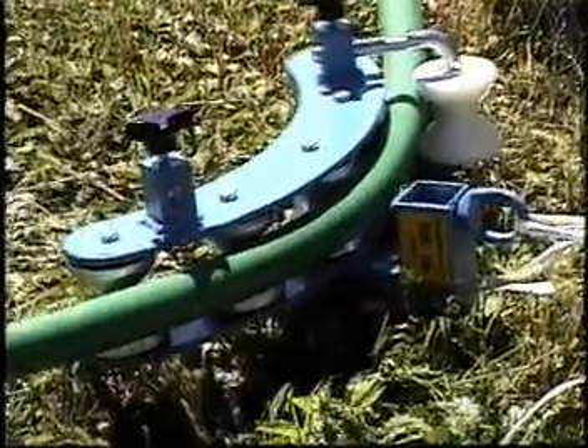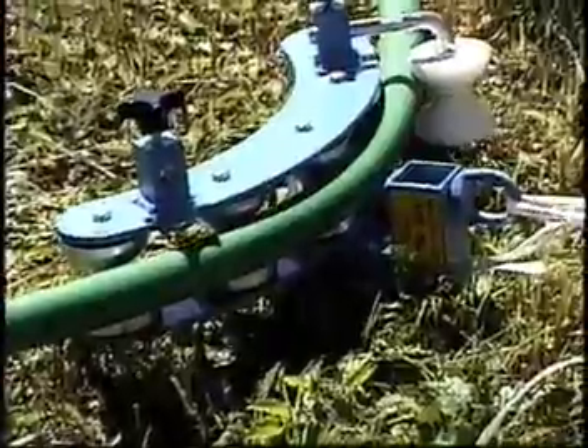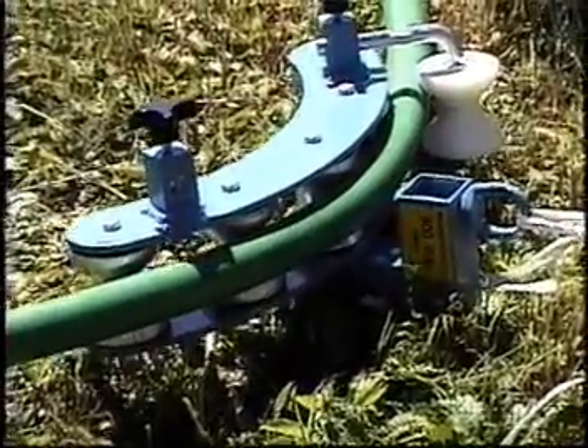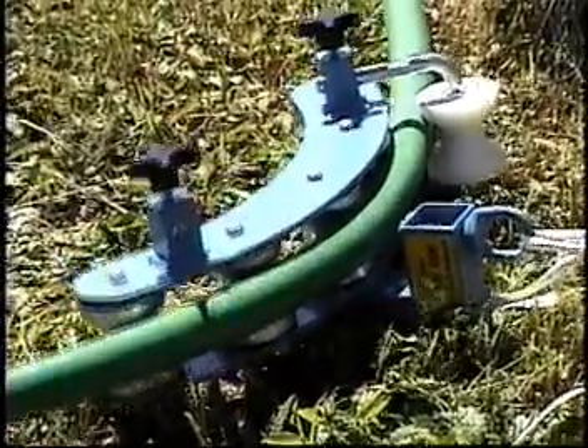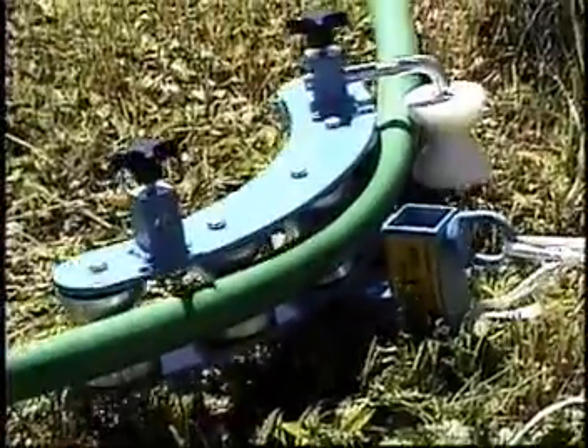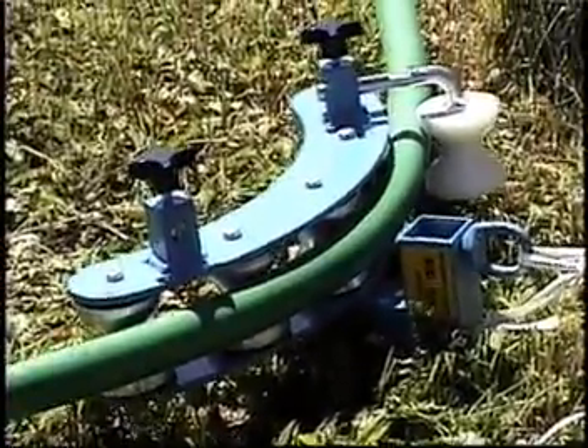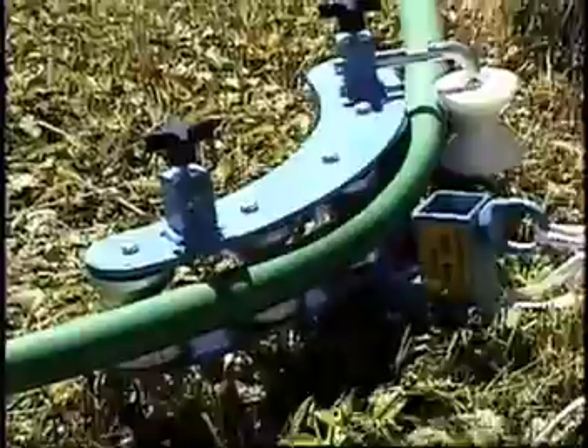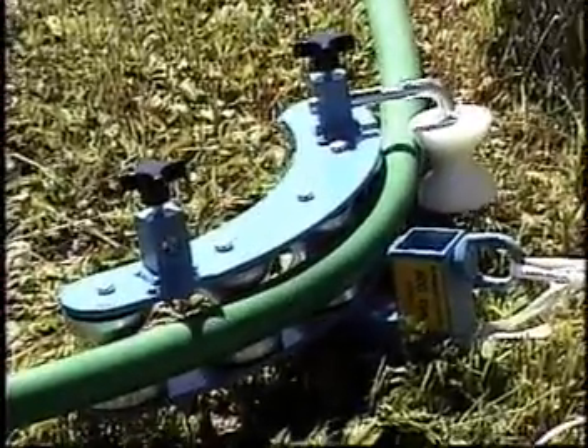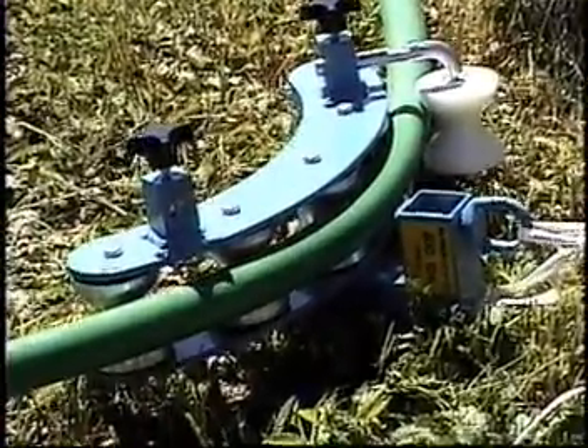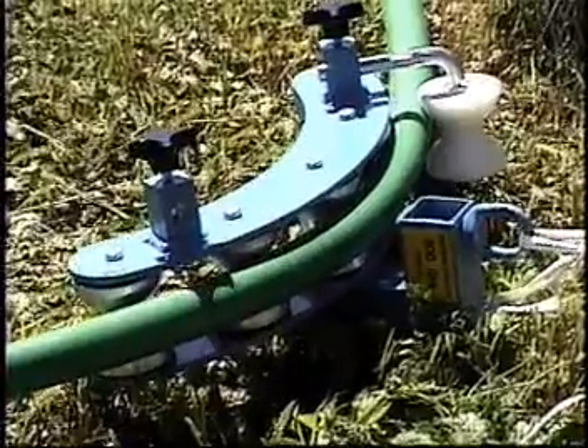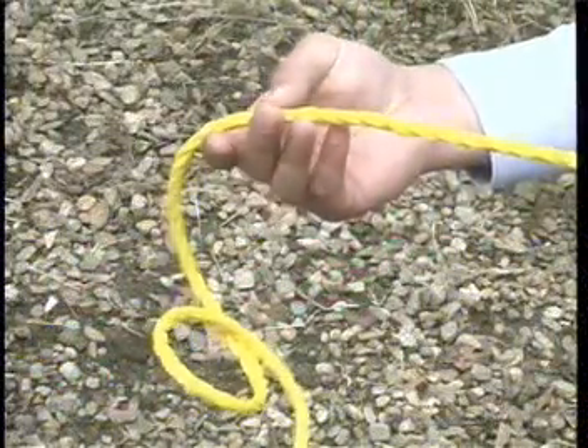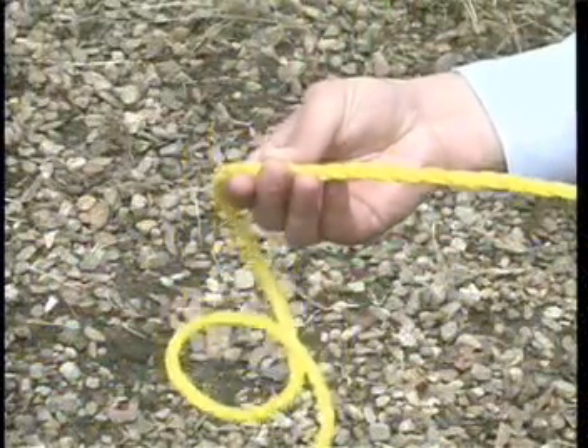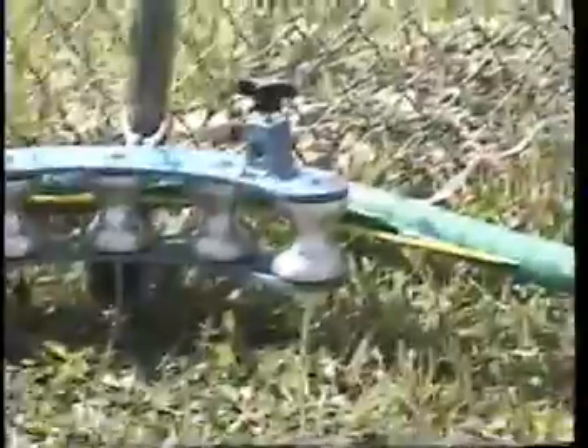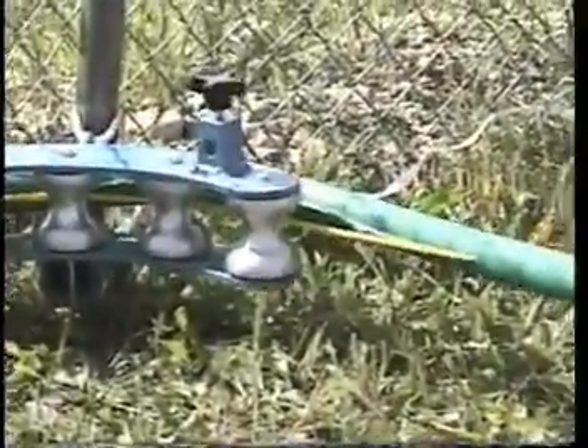Seeing is believing, but you can actually hear how smoothly and effortlessly the pre-lubricated Muletape glides through the interduct even around the 90-degree bends. And the cable moves just as smoothly, with no danger of snapback, thanks to Muletape's low elongation properties. Next, the 3/8-inch polyrope was tested, using the same equipment and identical parameters. You can hear the difference immediately.